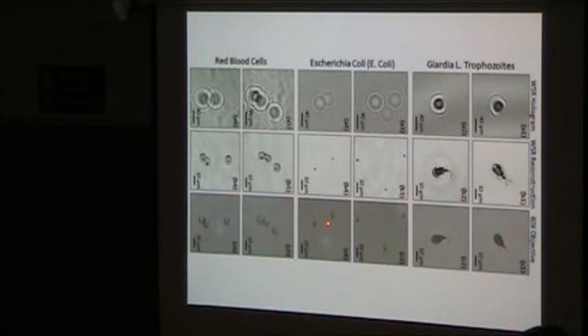So in this black box here, which changes the design to be a super resolved microscope, all we employ is a microcontroller, which is a very inexpensive processor, $3 per piece. It controls 23 inexpensive light-emitting diodes, so that at a given time, only one of the LEDs is on. So the static sample that's inserted from the side from this tray, that's seated above this CMOS sensor, is going to see a single LED illumination, and one at a time, I'll change the LED illumination so that this entire thing is shifting.